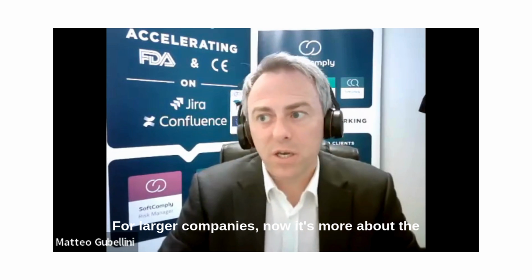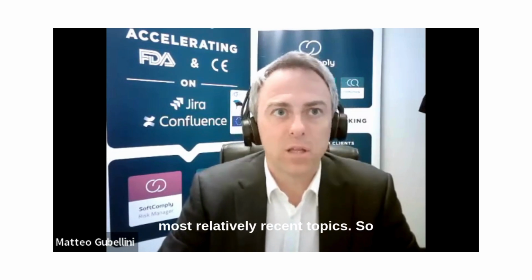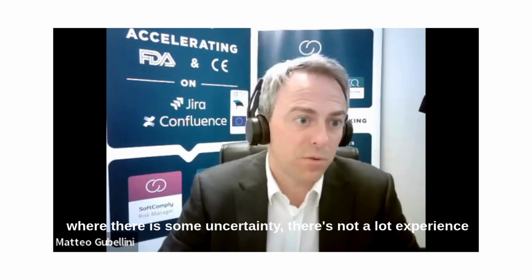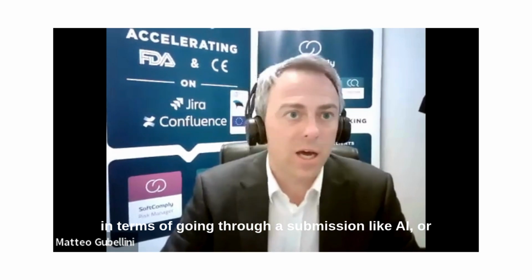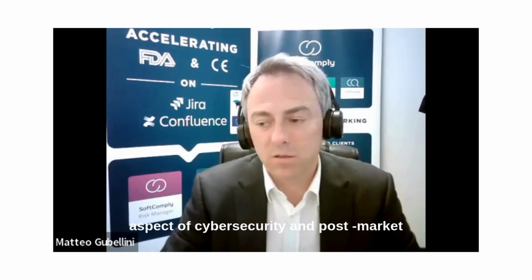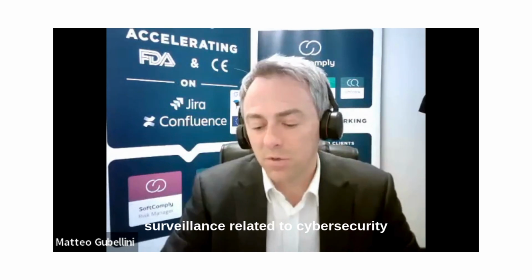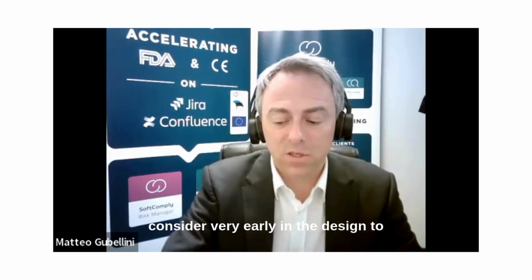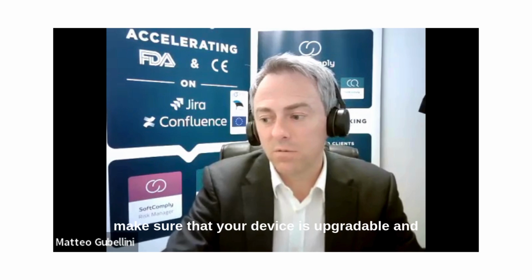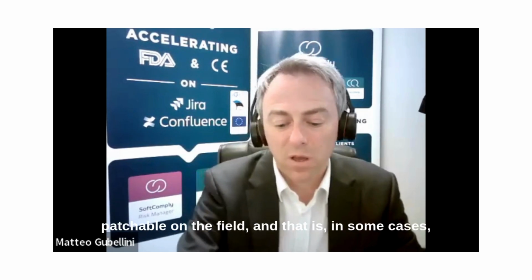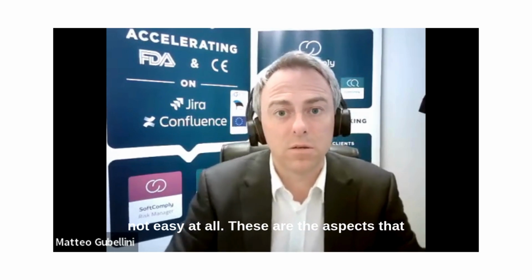For larger companies now, it's more about the relatively recent topics, where there is some uncertainty and not a lot of experience in going through a submission, like AI, or even, although it's not that recent, the aspects of cybersecurity and post-market surveillance related to cybersecurity. This is something you need to consider very early in the design to make sure that your device is upgradable and patchable in the field, and that is in some cases not easy at all.